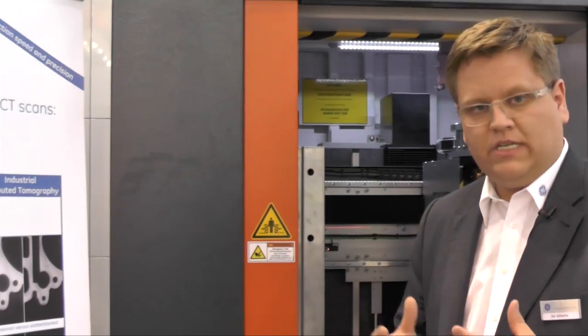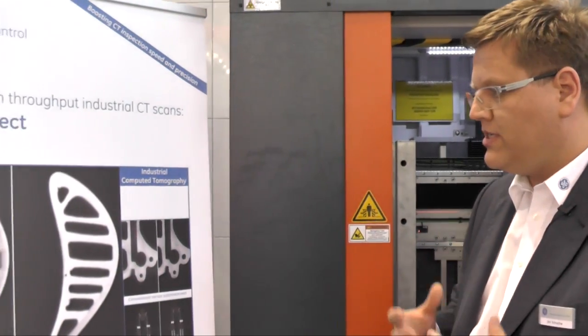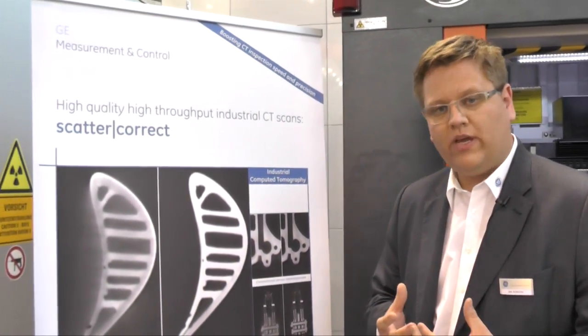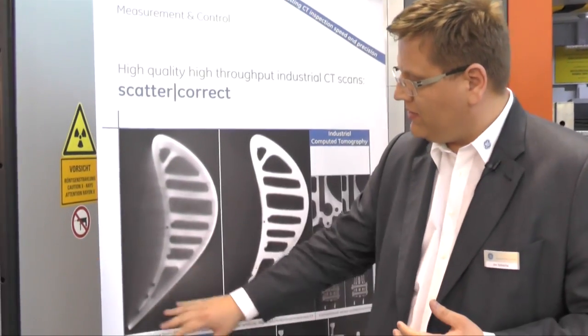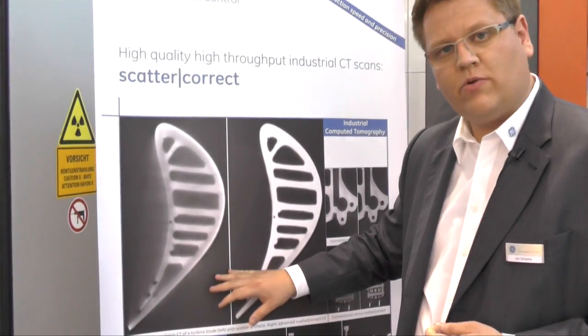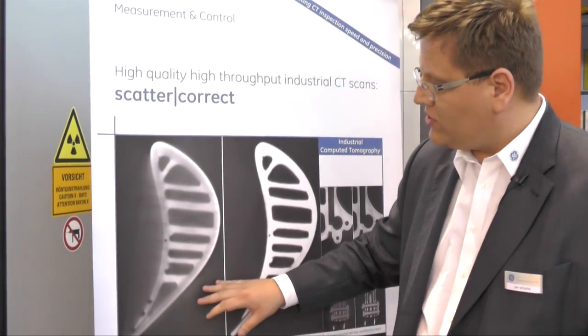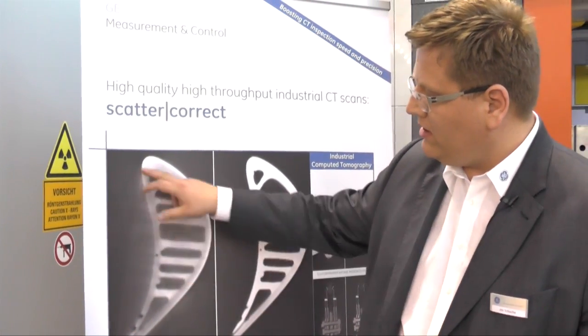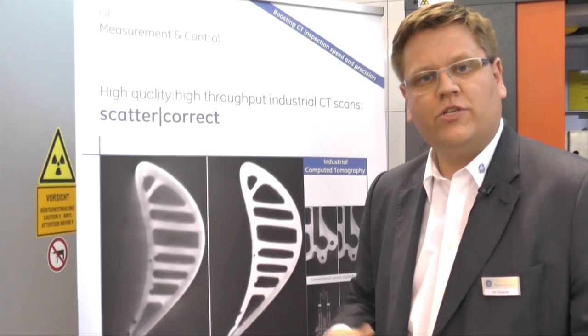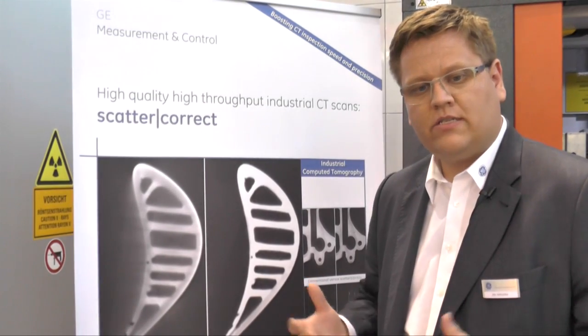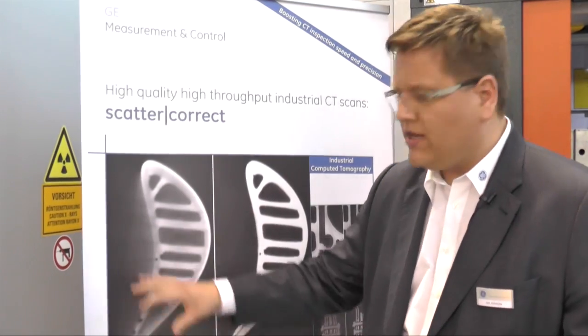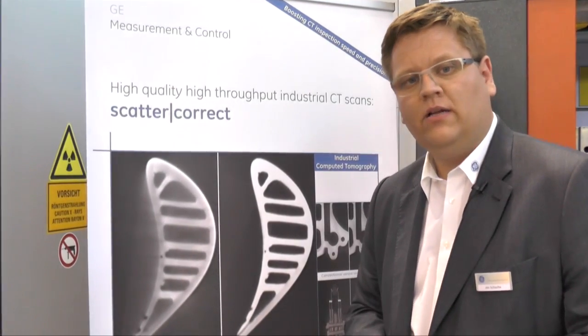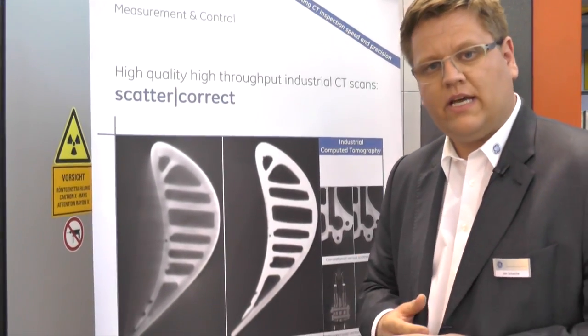As you might know from doing CTs on high-density materials or materials of large wall thicknesses, we suffer from scatter radiation. This example shall give you an idea of what scatter radiation is causing. We see here in the air grey values which simply do not exist — it is simply the effect from scatter radiation, a typical result from flat panel based CT scans.